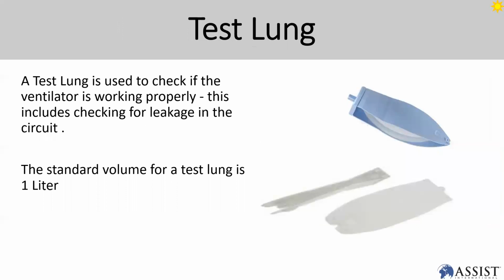Test lung. Okay, when you talk about test lung, it is one of the important devices that you use to check whether your ventilator is working or not. So normally, one of the best things to do is to test them using a test lung before you use it on the patient. That's what clinical people do. In hospital, when you go to the department, you're going to see they test with the test lung. If the ventilator is working properly, then only they're going to use it on the patient. So this is to prepare the ventilator unit for the patient.